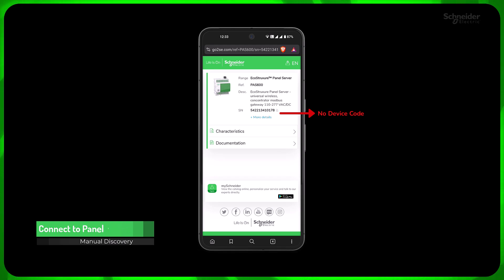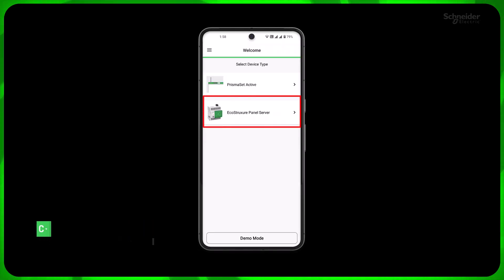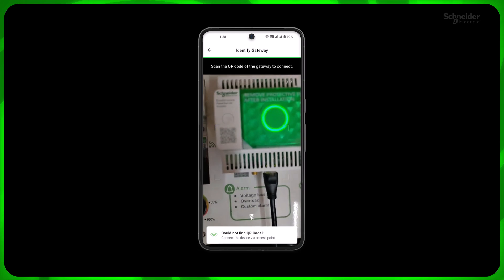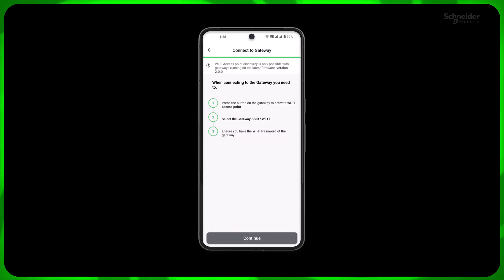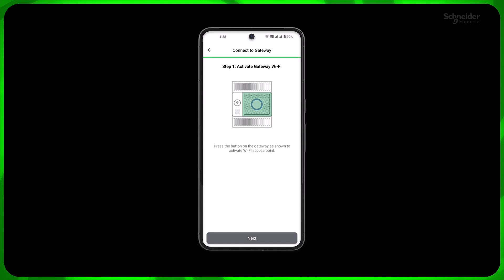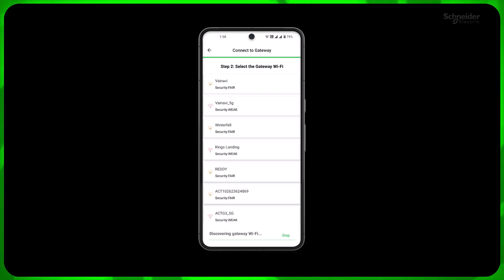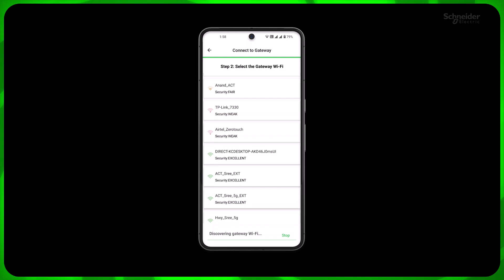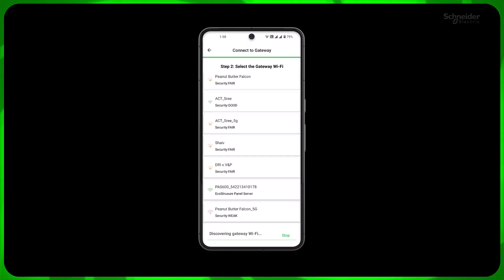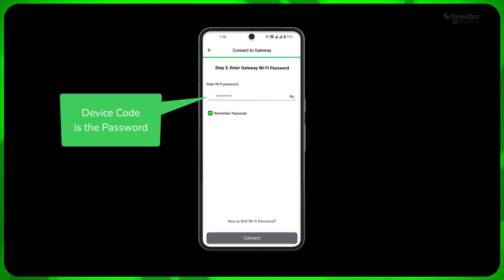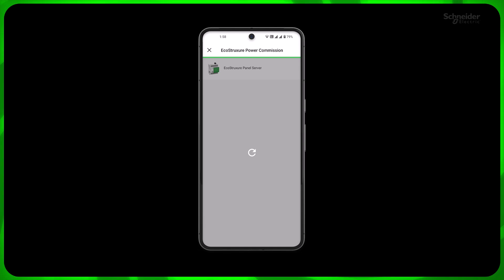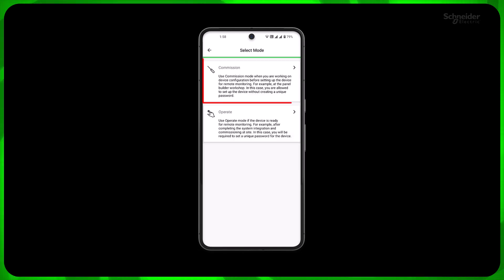For earlier versions of panel server with no device code included in the QR code, connect manually by selecting Manual Discovery or Could Not Find QR Code. Activate the panel server access point. The SSID will carry the model and serial number of your panel server for proper identification. Select the respective access point and enter the device code as password. Select the commission mode to reach the overview screen.